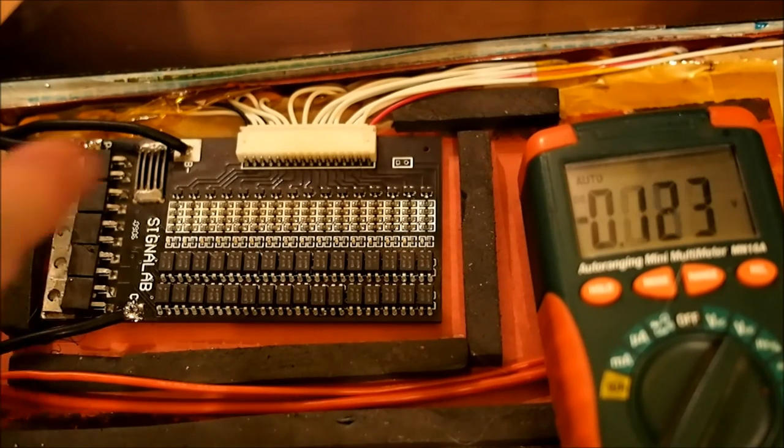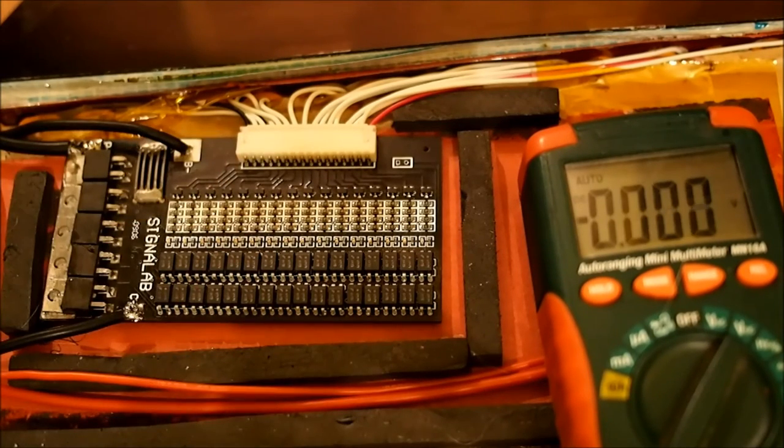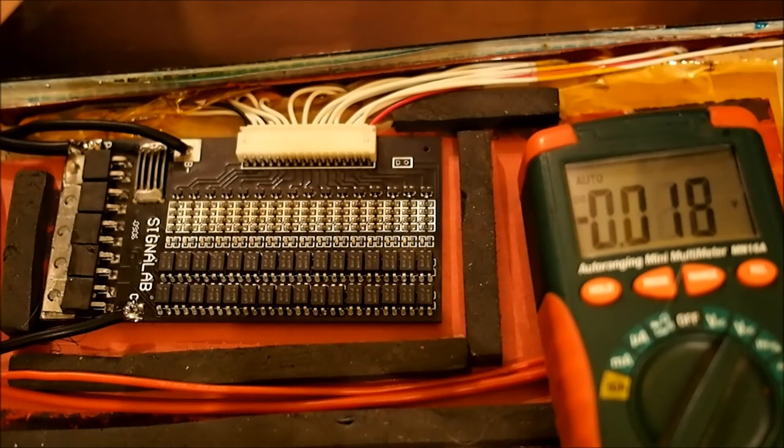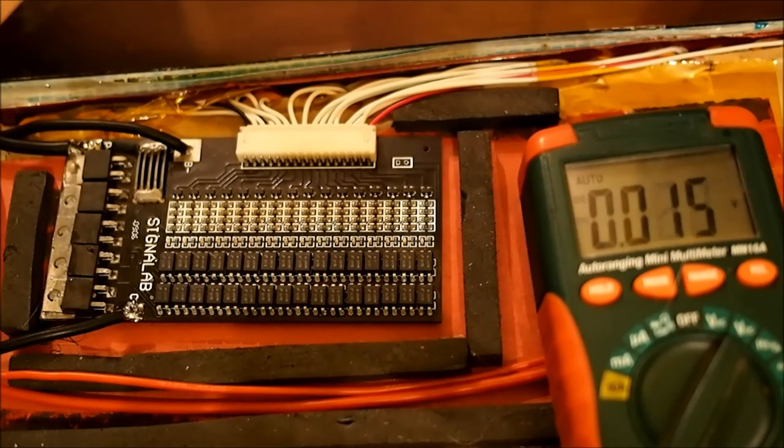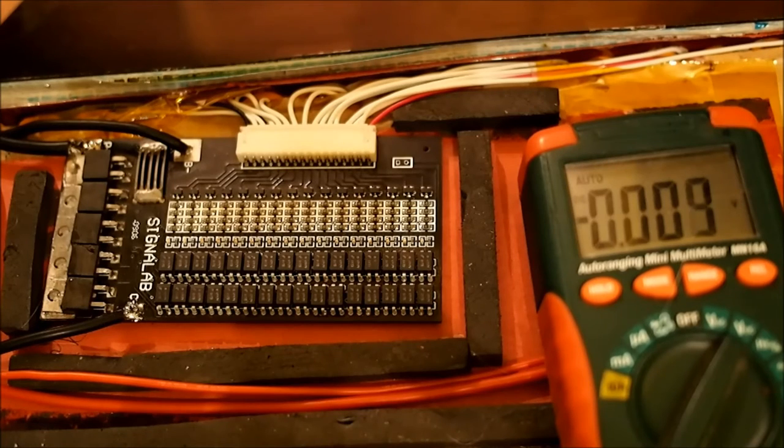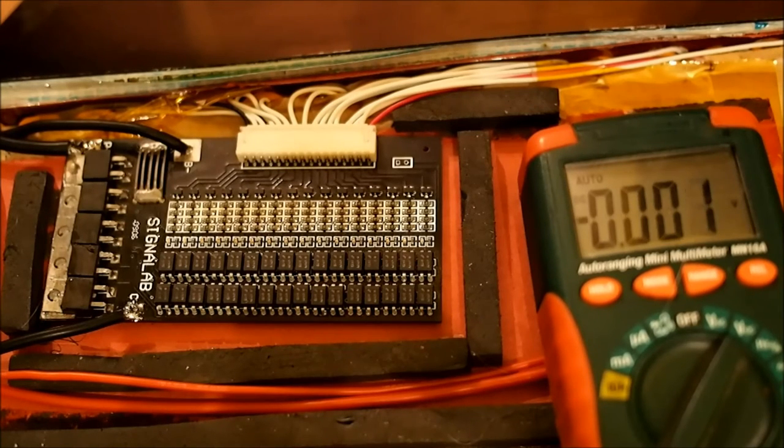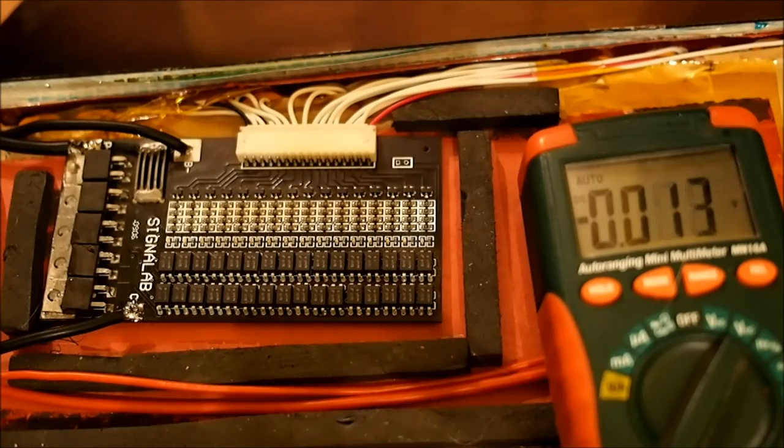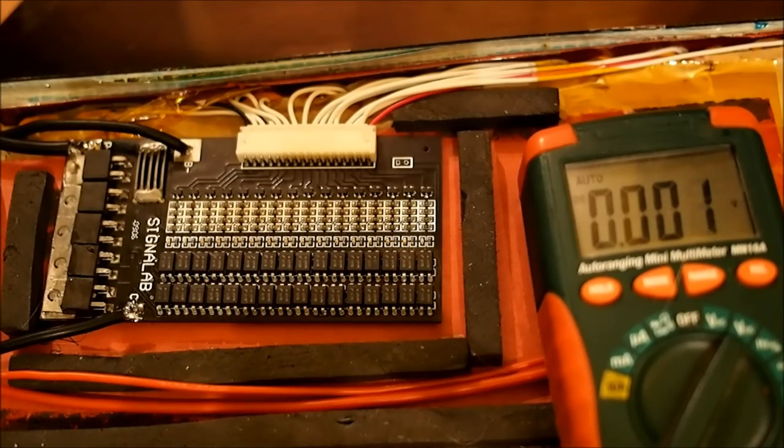If any of those is below 2 volts or is above 3.5, 3.6 volts, that indicates you may have a problem with the cells themselves in there. And it's generally not a good sign because that's a lot of work once you start tearing that apart. But it's still fixable. It just sucks.